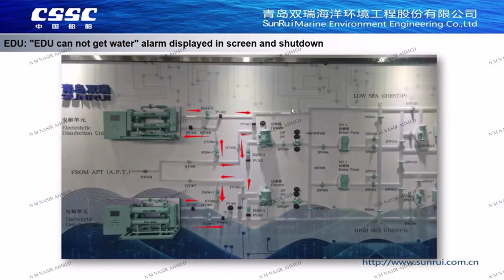We can see this ballast pump. Ballast pump takes water from the sea chest, and water goes through the filter, and water goes through the flow meter and the filter. EDU takes a branch of seawater from the filter outlet through the valves and the booster pump, treated by EDU. Then it is injected back to the main pipeline through the dosing pump.